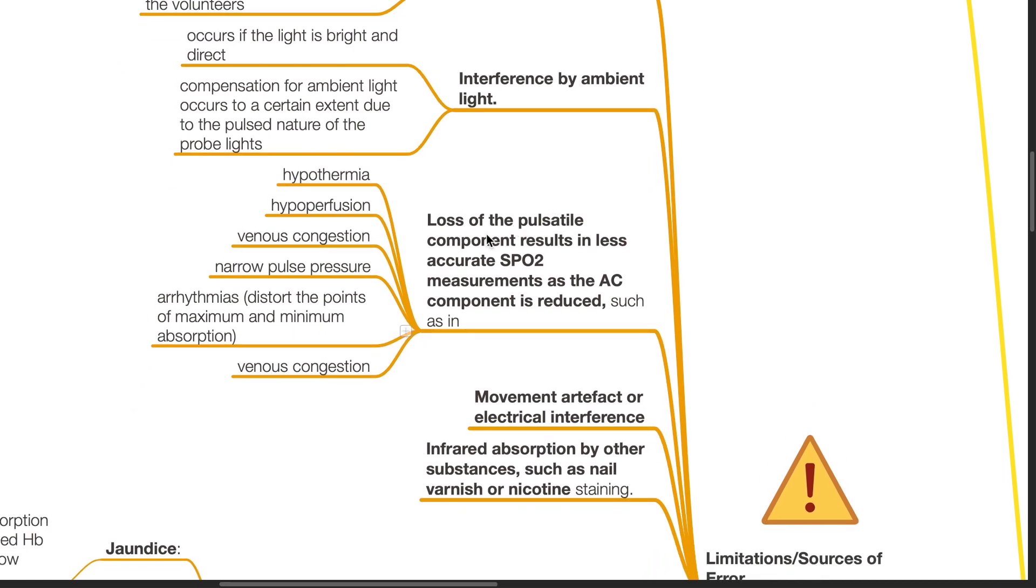Loss of the pulsatile component results in less accurate SpO2 measurements as the AC component is reduced, such as in hypothermia, hypoperfusion, venous congestion, narrow pulse pressure, arrhythmia which distorts the point of maximum and minimum absorption, and the use of arterial tourniquets and BP cuffs which causes hypoperfusion as well.